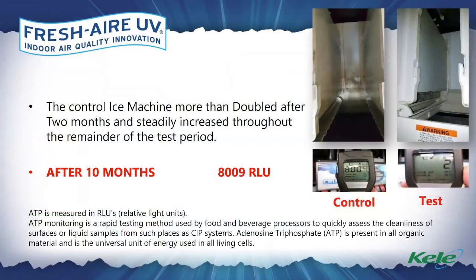Well, I know full well that this ice machine that we tested after 10 months of operation measured 8,009 RLUs. This ice machine is twice as contaminated as the worst thing that they could possibly have tested in that test, and that was 4,000 RLUs. The ice machine with the Fresh-Aire UV lamp went from 8,009 to 2. This is indicative of how effective UVC light is, and what possible contaminants could be growing in an ice machine. But certainly any dark, damp, cool environment will be prone to the same type of microbial growth. It just so happens that this is an ice machine where we're directly consuming the ice.